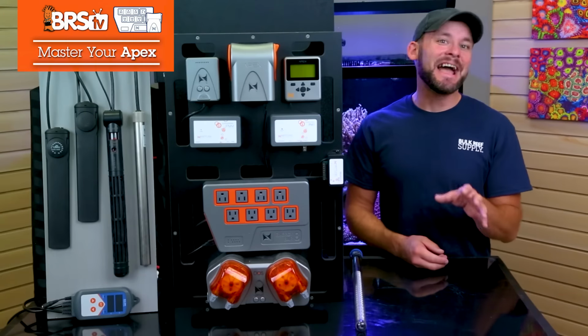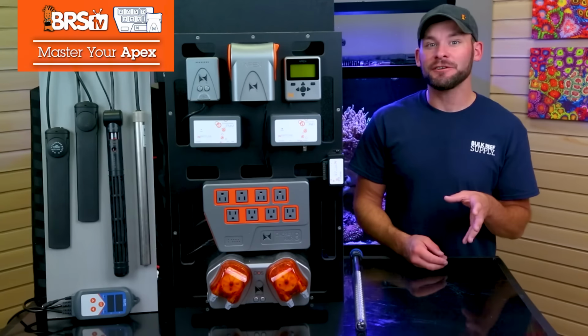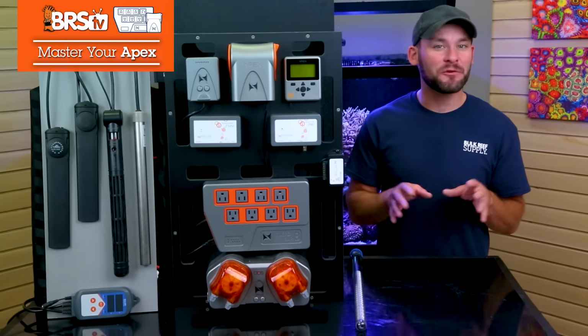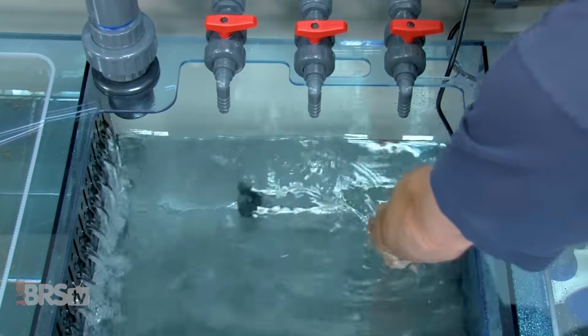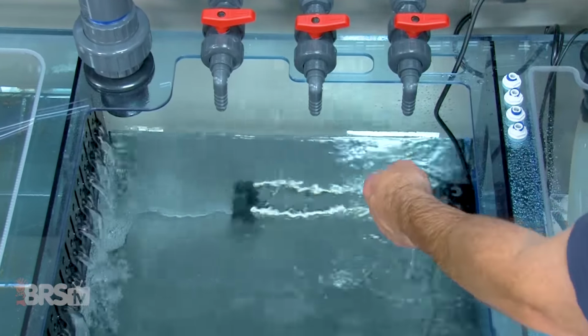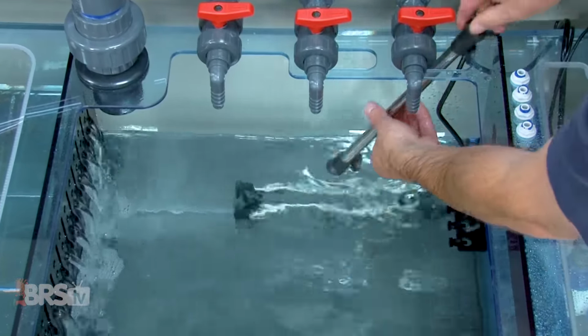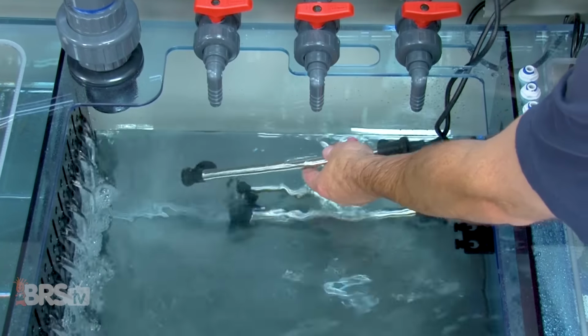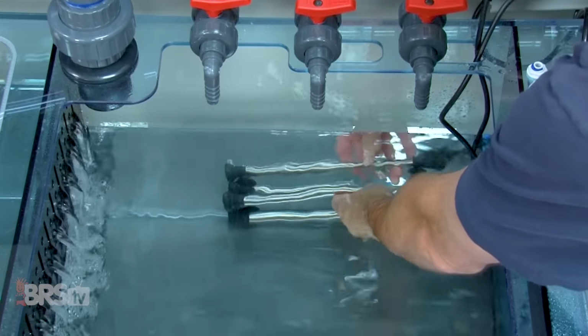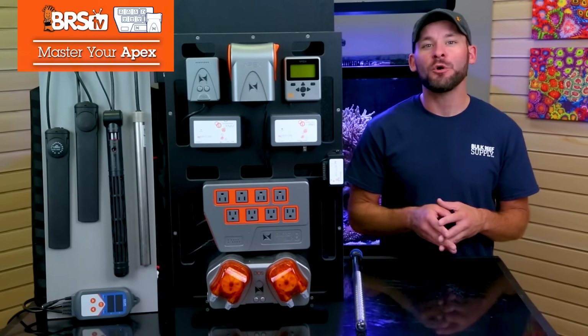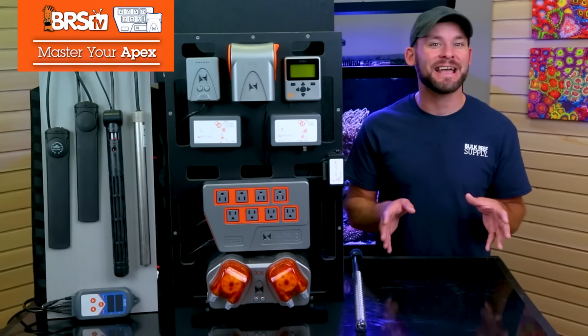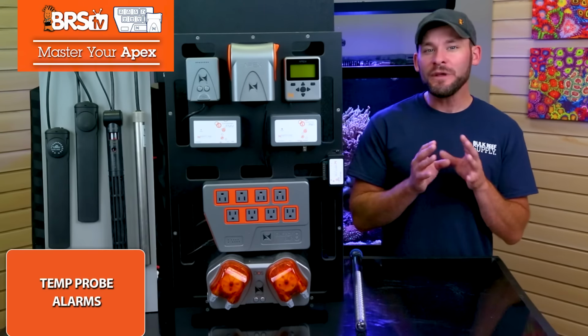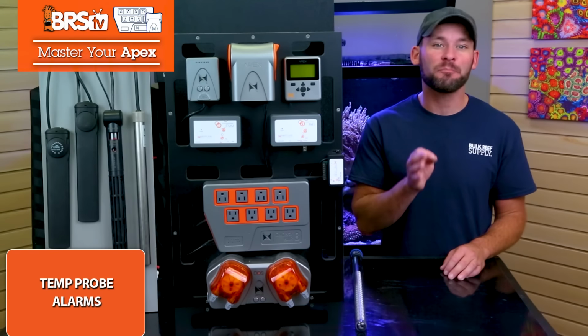You can follow that exact same process for your second redundant heater, trusting that if one of your heaters ever failed, and since they're only capable of 75% of your target temp, the backup heater would be able to keep some heat in the tank rather than the tank temp dropping too low. However, the real value is knowing that something's out of whack in the first place as soon as possible, which we will tackle next by setting up temp probe alarms.